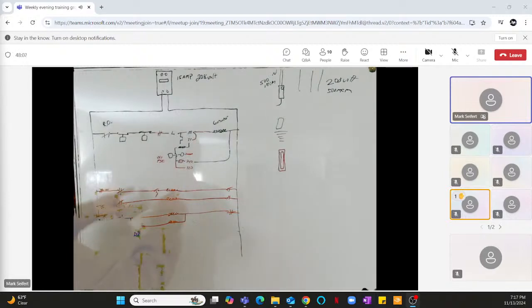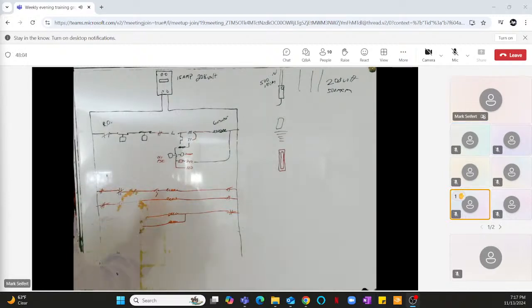This is where it goes out of the box and goes down to the case. Maybe there's something down at a service meat case or something. It's probably a T-stat. But you can know what you're looking at. You go in the motor room and you're like, I got power going out to it, because you can see the circuit. You can check it at the terminal strips or wherever. Just pull on wires. Look at it.